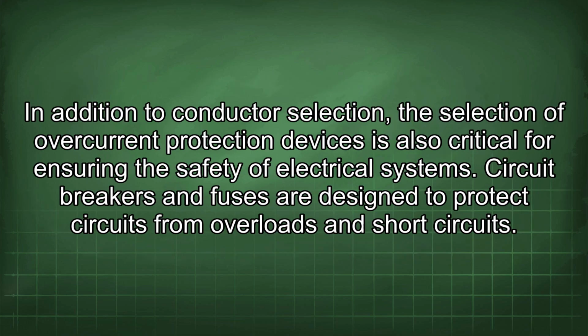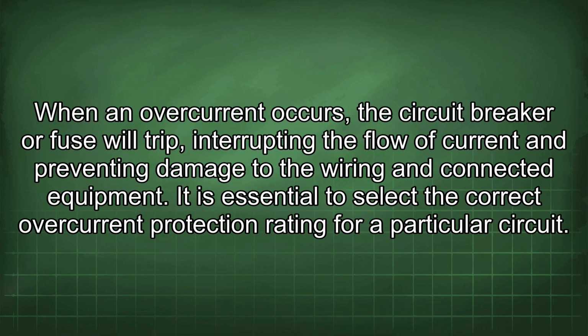In addition to conductor selection, the selection of overcurrent protection devices is also critical for ensuring the safety of electrical systems. Circuit breakers and fuses are designed to protect circuits from overloads and short circuits. When an overcurrent occurs, the circuit breaker or fuse will trip, interrupting the flow of current and preventing damage to the wiring and connected equipment.